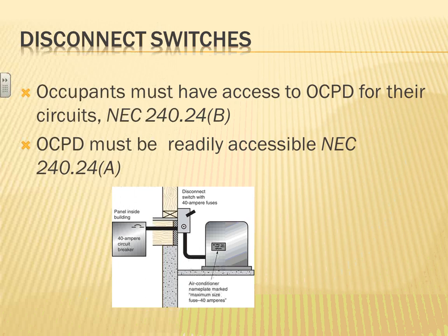Overcurrent protection devices, including fuse disconnects, must be readily accessible, with some exceptions. Occupants must have access to them.